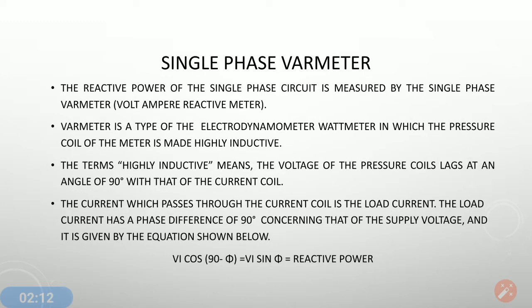We will first discuss the single phase VAR meter. The reactive power of the single phase circuit is measured by a single phase VAR meter or volt-ampere reactive meter. This type of VAR meter is basically an electrodynamometer wattmeter in which the pressure coil of the meter is highly inductive in nature. In the standard electrodynamometer wattmeter, the pressure coil is inductive but not highly inductive, whereas in the single phase VAR meter, this pressure coil is highly inductive.